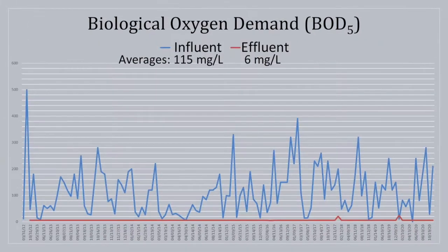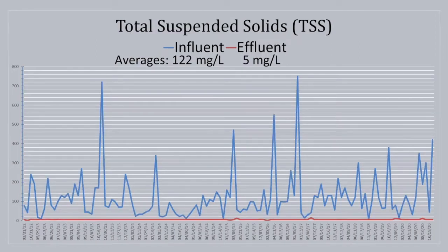Looking specifically at BOD: the inflow shows typical variability seen from any treatment plant — up and down for the influent. But look at the effluent line — the red line on the bottom. It is flat. It is stable. It is robust, very consistent treatment, which is what we'd expect for a sand filter. TSS shows the same pattern: influent coming in over 100 mg/L, but the effluent line is flat on the bottom, averaging five mg/L for years and years. We're not seeing any seasonal changes in the effluent being discharged.